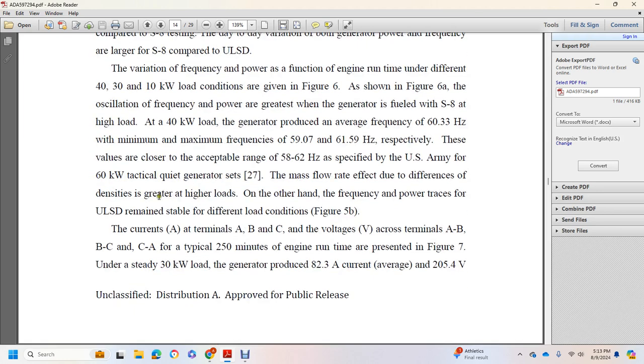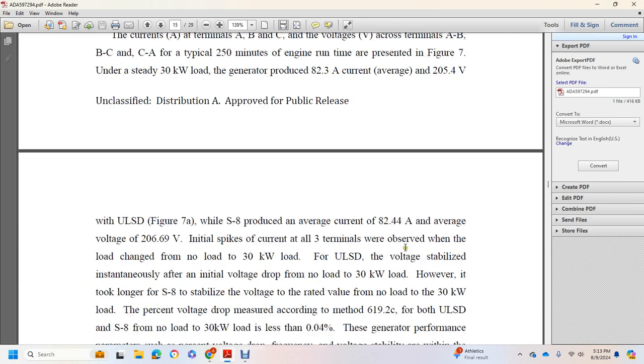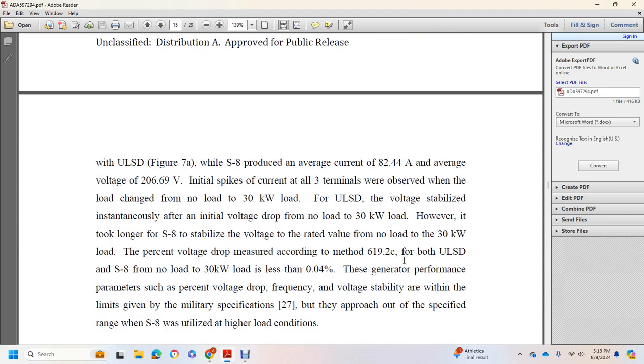Figure 5b. The currents A in terminal A, B, and C, with the voltage V across terminals A and B, B and C, and C and A. Typical 250 minutes of engine runtime are presented in figure 7. Under a steady 30 kilowatt load, the generator produced 82.3 amps average current and 205.4 volts with ultra-low sulfur diesel, figure 7a, while the S8 produced an average current of 82.44 amps and an average voltage of 206.69 volts.